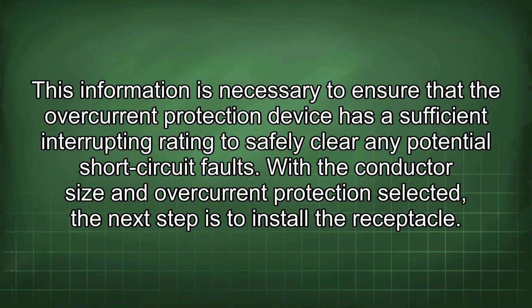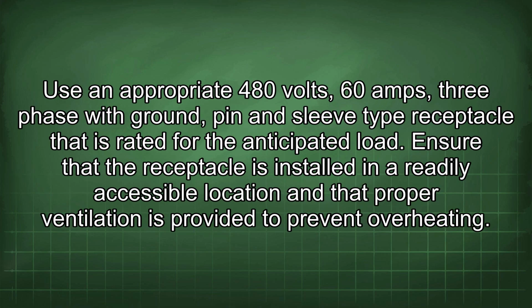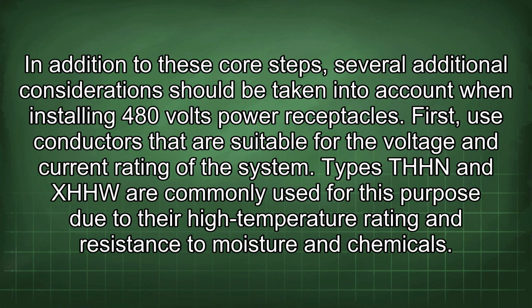With the conductor size and overcurrent protection selected, the next step is to install the receptacle. Use an appropriate 480 volts, 60 amps, 3-phase with ground, pin and sleeve type receptacle that is rated for the anticipated load. Ensure that the receptacle is installed in a readily accessible location and that proper ventilation is provided to prevent overheating. In addition to these core steps, several additional considerations should be taken into account when installing 480 volts power receptacles. First, use conductors that are suitable for the voltage and current rating of the system.